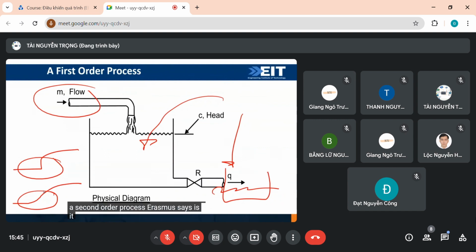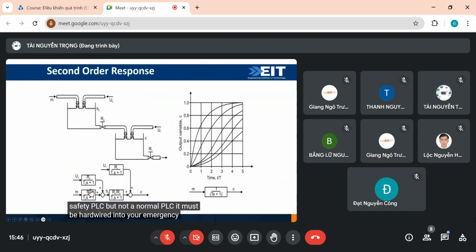Erasmus asks, is it advisable to use power relays in place of interlocks? It's entirely up to you, but remember, if you have a safety system such as an emergency stop, it has to be hardwired into your system. You can't put it into a normal PLC, only into a safety PLC. It must be hardwired into your emergency system.